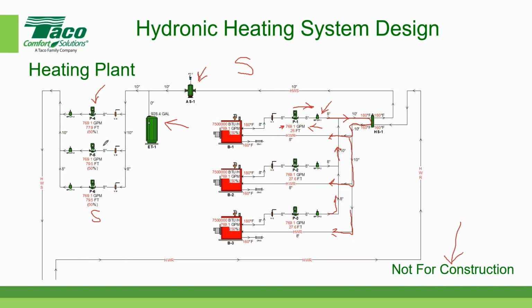these are variable speed pumps. So depending on the demand of the system, I could run any combination of these. But in general, since I've sized them for 50%, I would only run two pumps at a time, perhaps this pump and this pump initially, and then this third pump here would be my standby. If I should lose any one of these pumps, then my standby pump would become operational, so I would never lose capacity in the system.